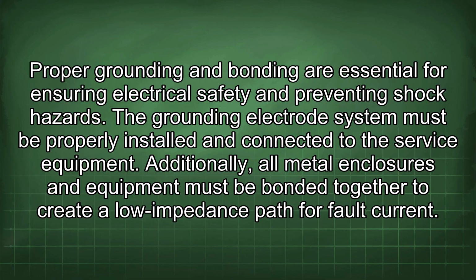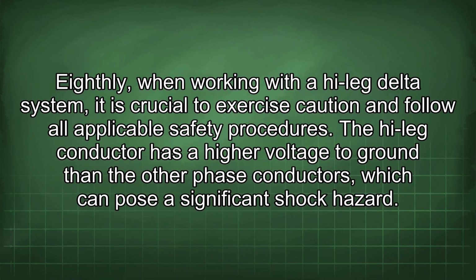The grounding electrode system must be properly installed and connected to the service equipment. Additionally, all metal enclosures and equipment must be bonded together to create a low impedance path for fault current. Eighthly, when working with a high-leg delta system, it is crucial to exercise caution and follow all applicable safety procedures.